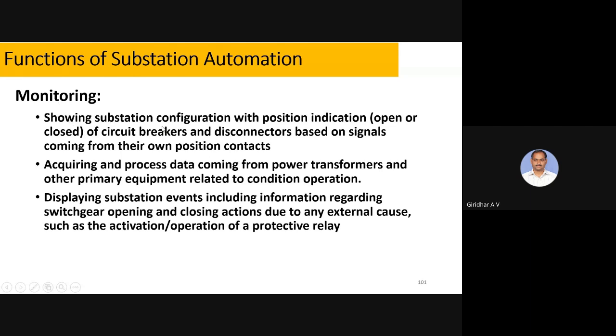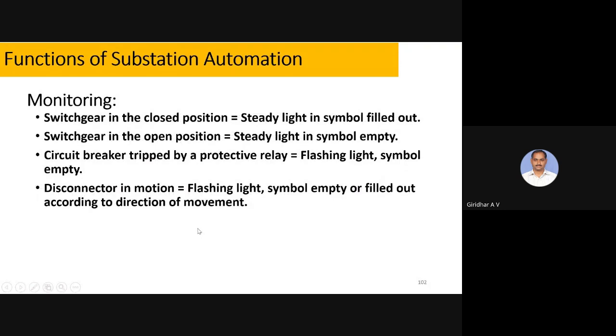So you can see monitoring aspects: position indication, open and closed circuit breakers and disconnectors, and acquiring process data from power transformers, along with various related data we can get in the substations, like dissolved gas analysis, partial discharges from the measurements, and moisture measurement. So like that, various data we can get and can be analyzed. And you are also displaying substation events in the substation control room, all the actions, everything that is happening. So you can see the monitoring aspect.